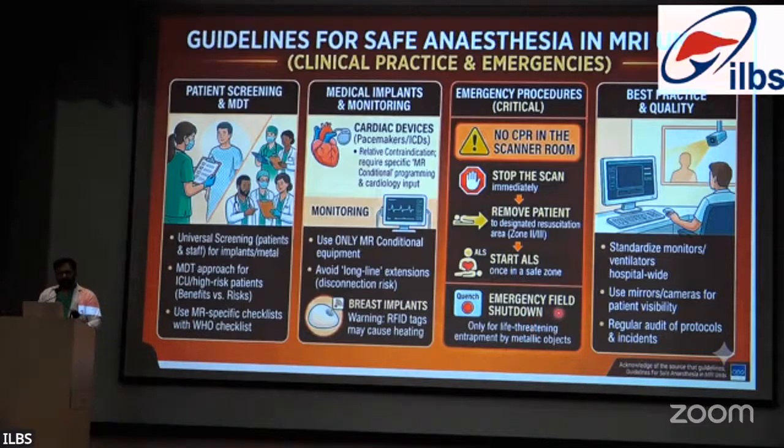During an emergency field shutdown, which is called quenching, there is a risk of hypoxia because of the helium release. So it should be taken care of and the patient should be removed as soon as possible. So the best practice is to use proper audits of protocols and incidents.